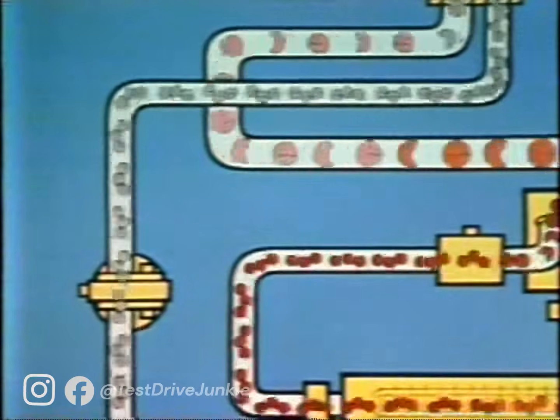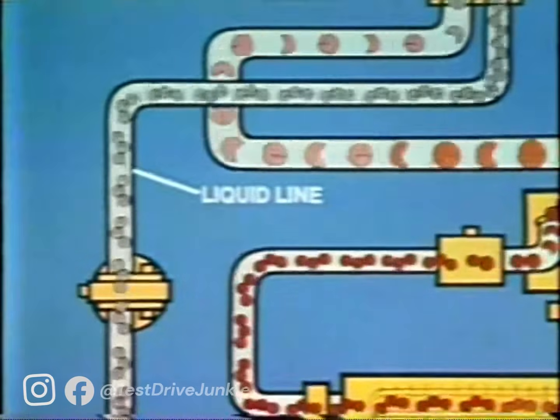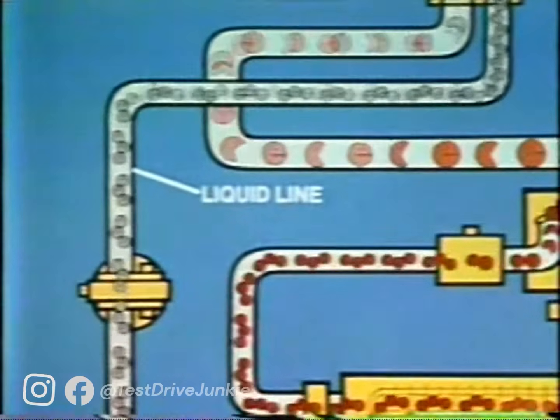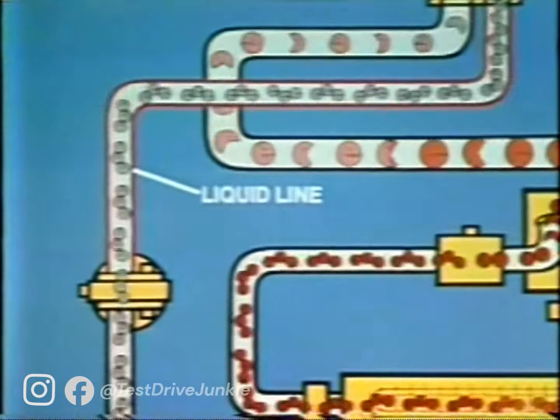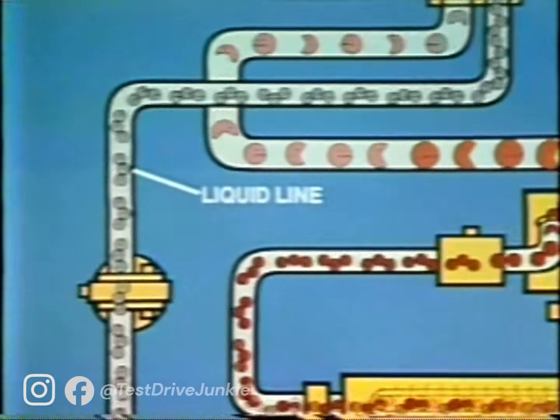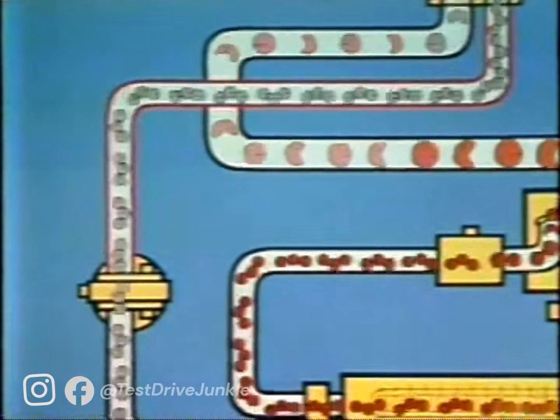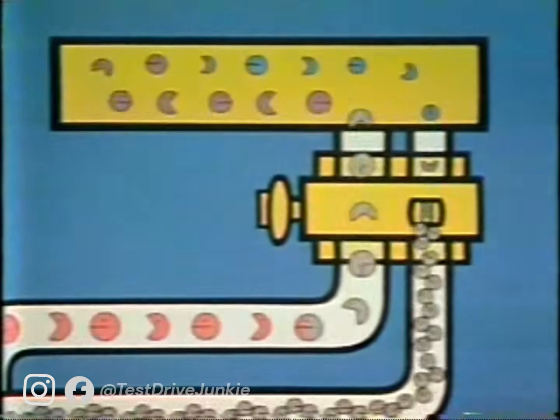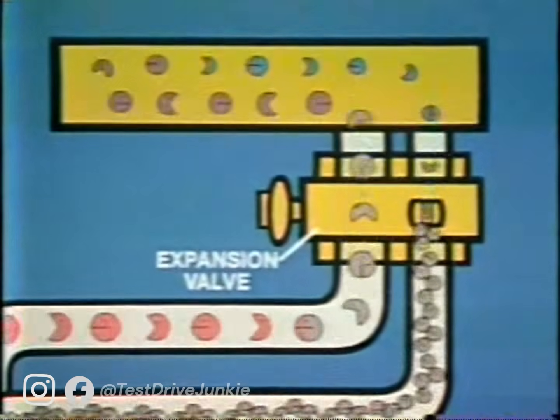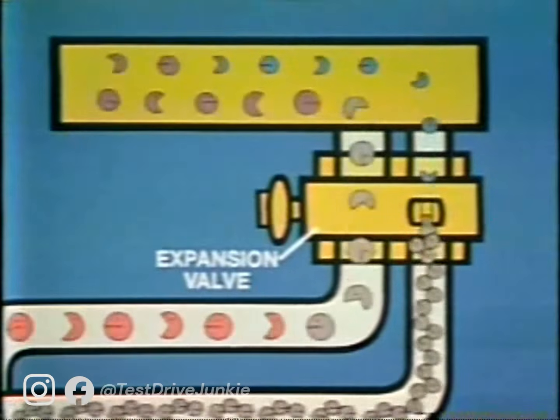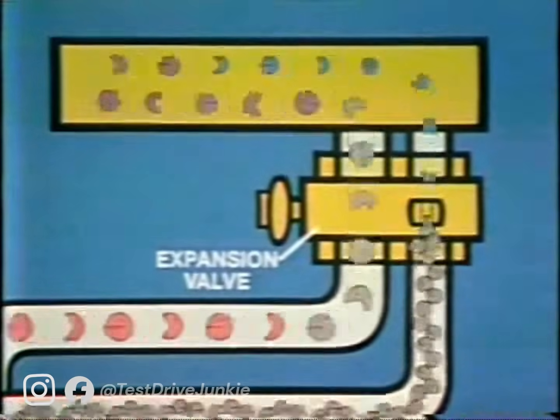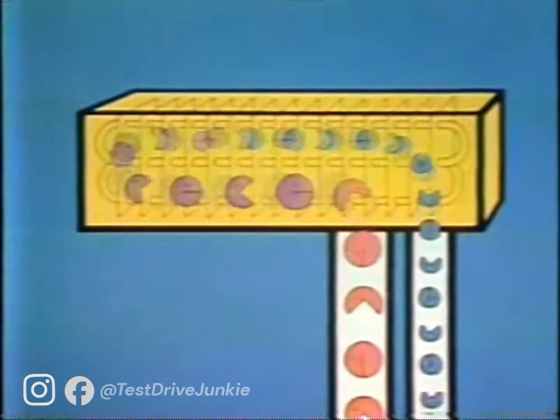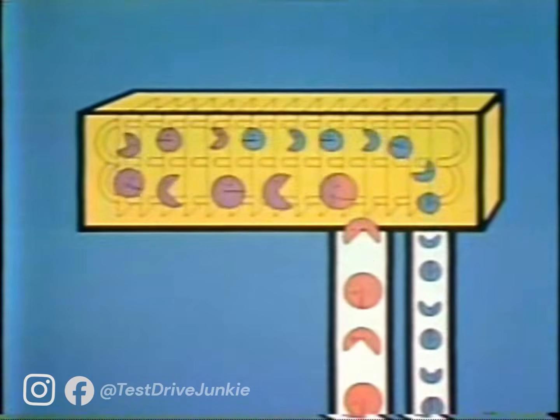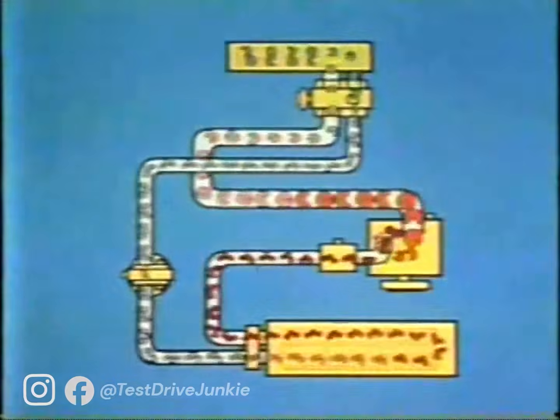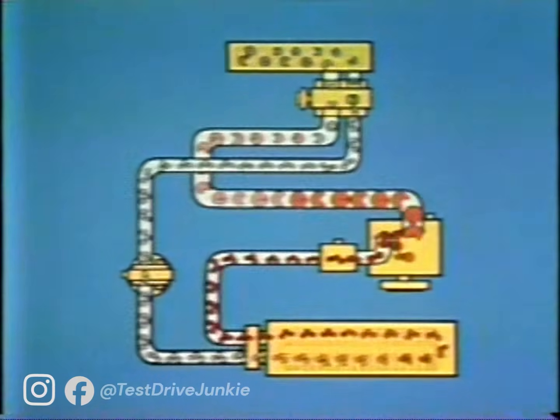From the filter dryer, the refrigerant travels through the liquid line. Because the molecules are packed together so tightly, the heat energy left in the refrigerant is concentrated, making the line warm to the touch. The liquid refrigerant begins to vaporize at the expansion valve, which controls the rate of evaporation by metering the refrigerant flow. Vaporization continues throughout the evaporator, completing the cycle. These principles of operation are basic to all air conditioning systems.